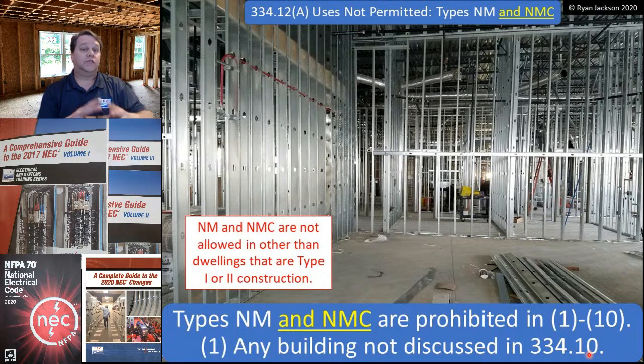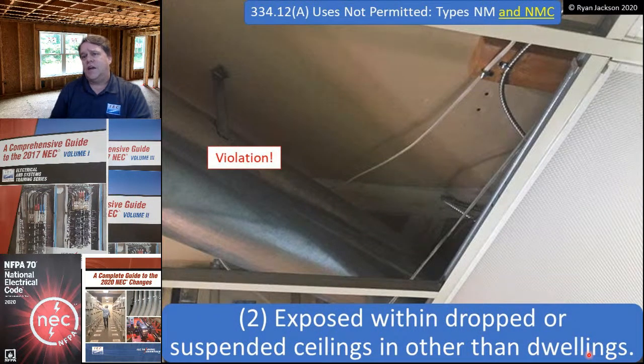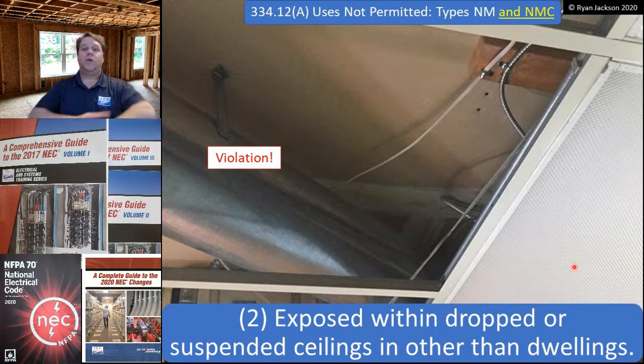Uses permitted: dwellings, multifamily dwellings, other than dwellings. Number two, this was changed back in 1999. You also cannot use NM cable exposed within dropped or suspended ceilings in other than dwellings. Now, I've had a lot of people ask me why over the years. Why can't you put it above the ceiling in a commercial building? Well, the reason for that, from all of my research, is you guys might remember, back in the 90s, there was a three-story cap on where you could use NM cable. You can use it up to three stories, that's it. If it's four stories, no Romex.